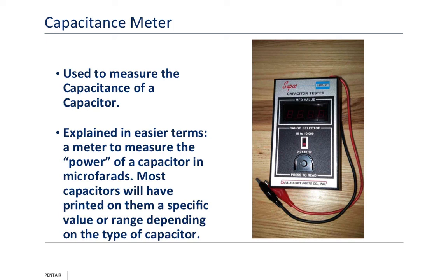A trick you can do, and that's why you want to check it: if the capacitors are getting beat up, you can buy ones with better insulation. Meaning that if it's rated for 370 volt, buy one that's rated for 460 volt. The higher the voltage they're rated to handle, the more insulation there is. Get one rated 86 microfarads or very close to that. If you find one rated for 92 microfarads, you can always go up a little bit. Don't go down. But get one rated for a higher voltage capacity, and you have better insulation and usually get longer runtime out of that capacitor.